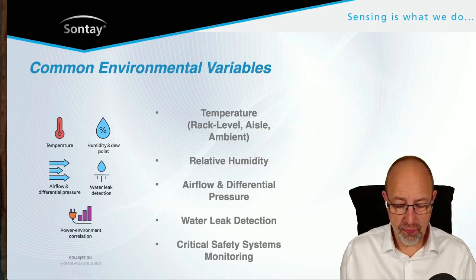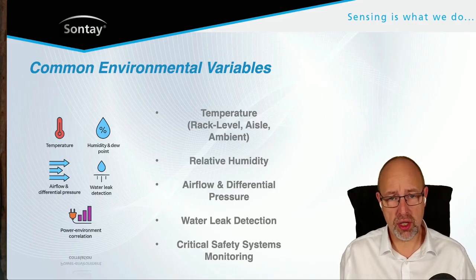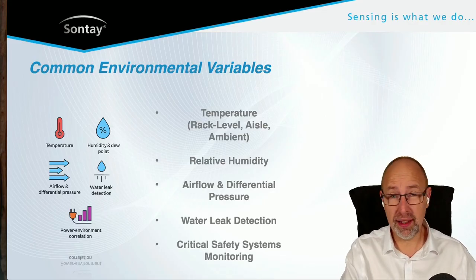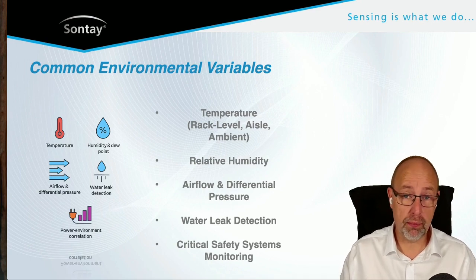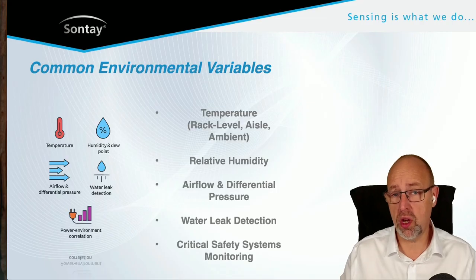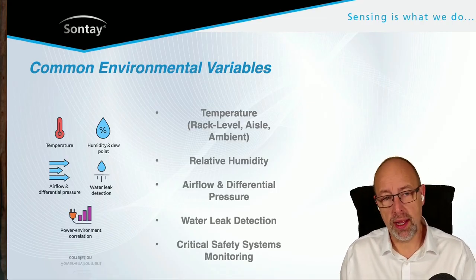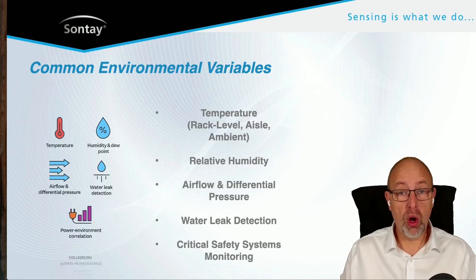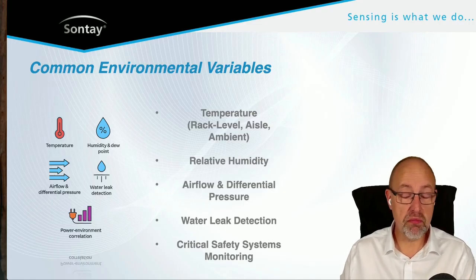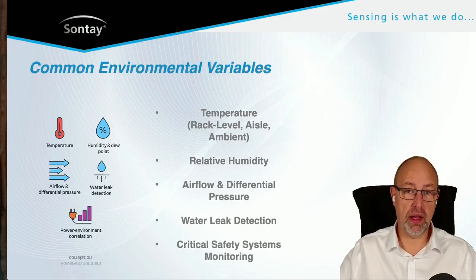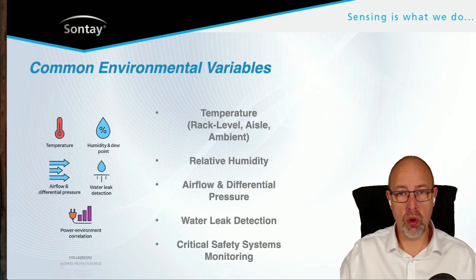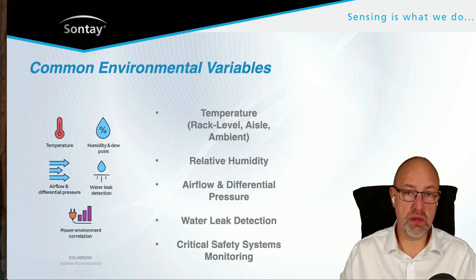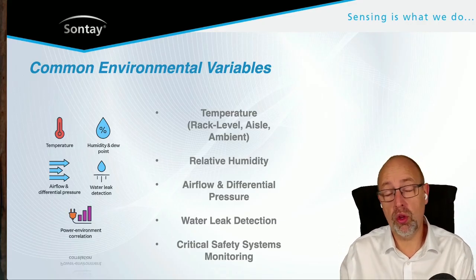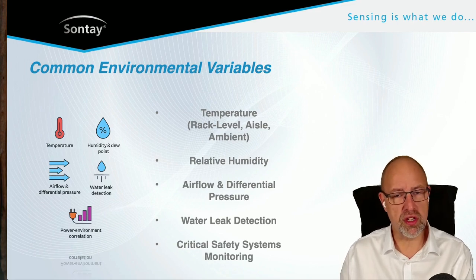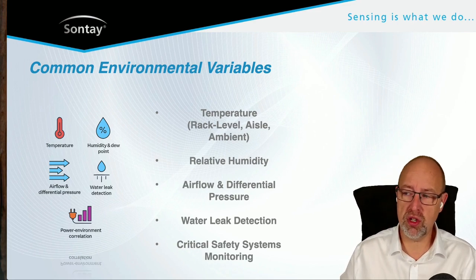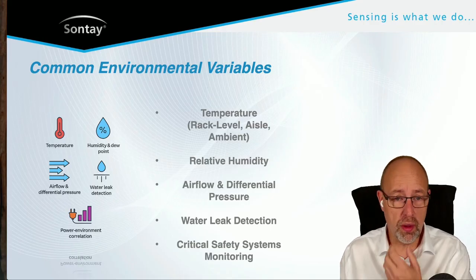Airflow and differential pressure. Now, the differential pressure side of it, that can come in with pumps. We have flow monitoring for our pump sets as well. So there's a lot of things that can factor into the water side of this. But in terms of the airflow monitoring, you would normally want to see some kind of pressure regime maintained in a data suite environment, because you want to have that under positive pressure, so that when someone opens a door, it doesn't suck a load of dirt in, which could affect the systems inside. You want air to be pushed out. So knowing what the pressure regime is, certainly not as important as laboratories, but you certainly want to ensure that you have the correct pressure regime in your data center, as much as you would do anywhere else.